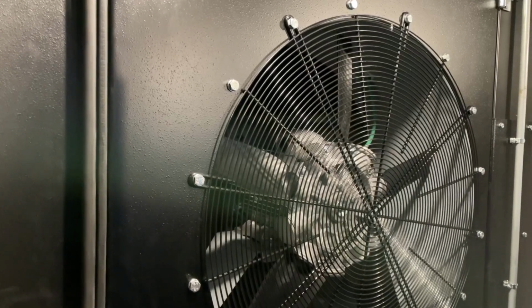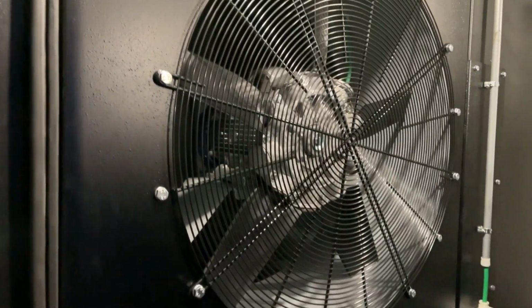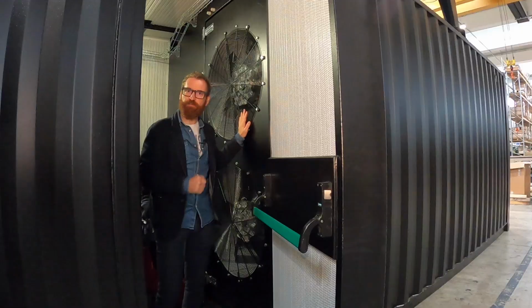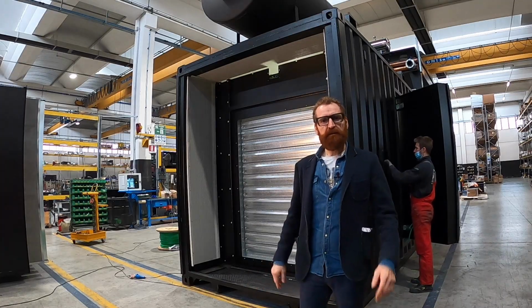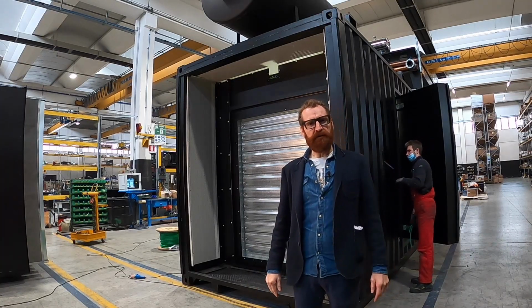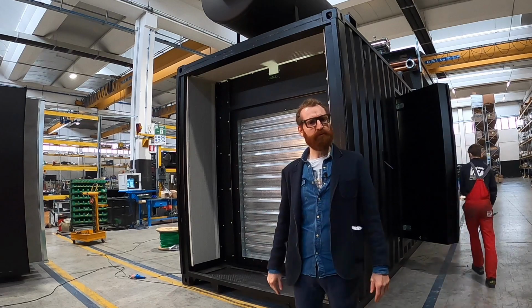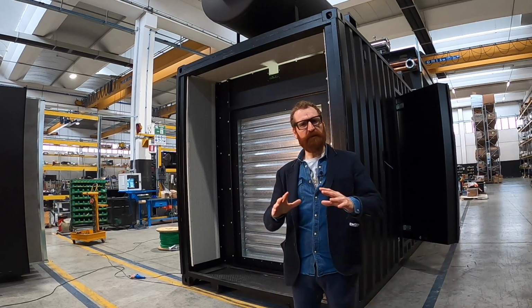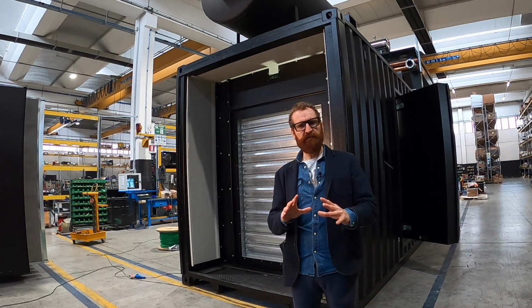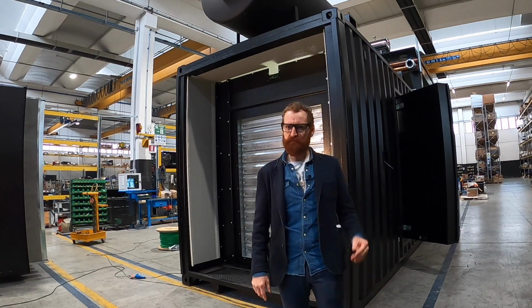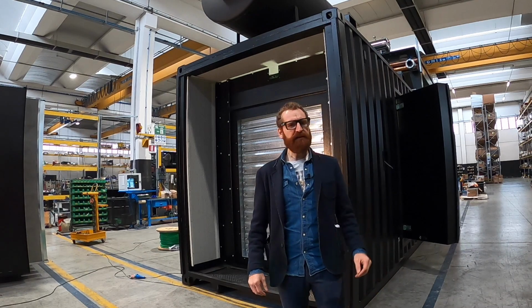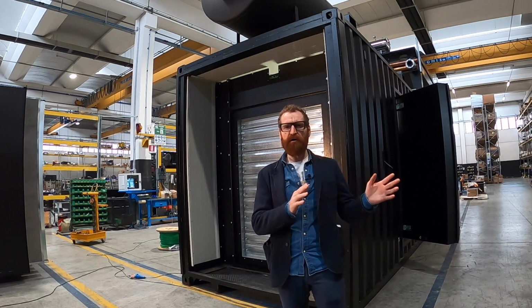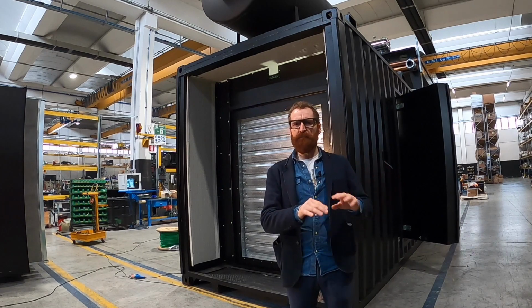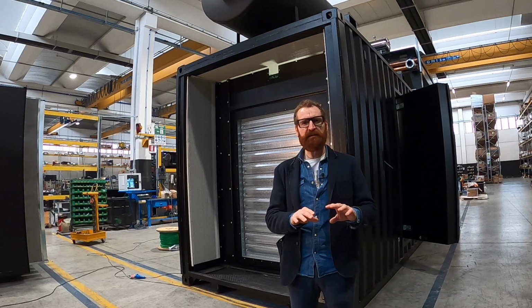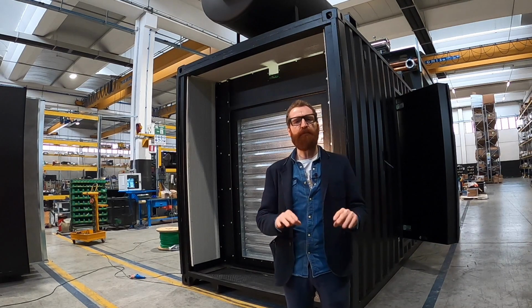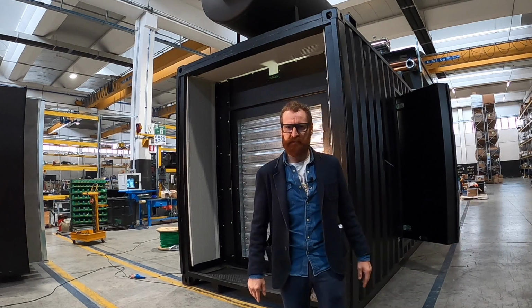Special ventilators are used to cool the container and avoid overheating problems. The openings for air inlet and outlet are both provided with motorized louvers. This permits us to keep the container warm during the standby phase, especially during winter. A dedicated heater blows hot air inside the container and maintains a constant room temperature of approximately 20 degrees.